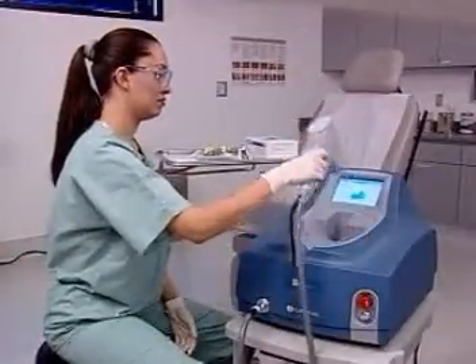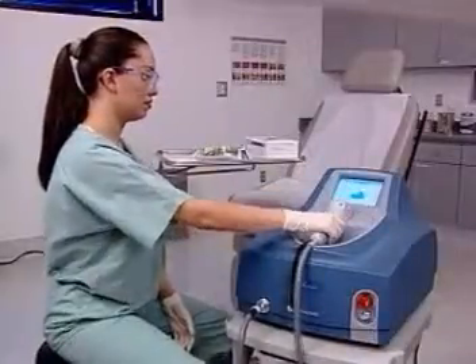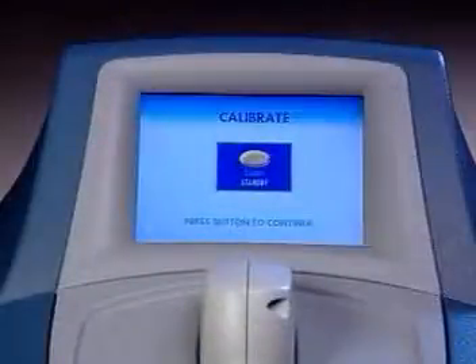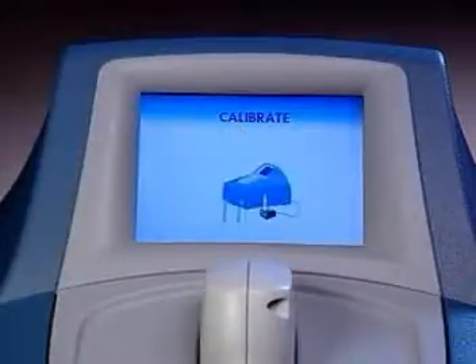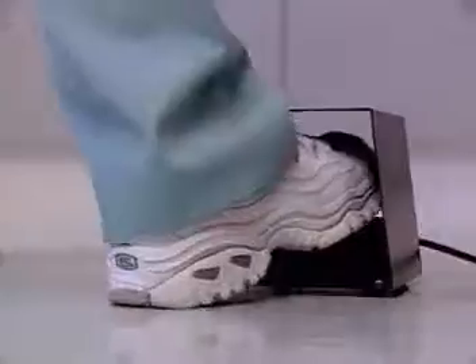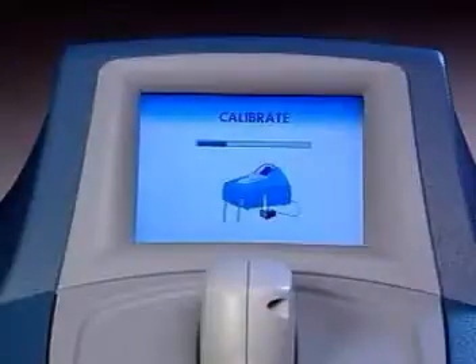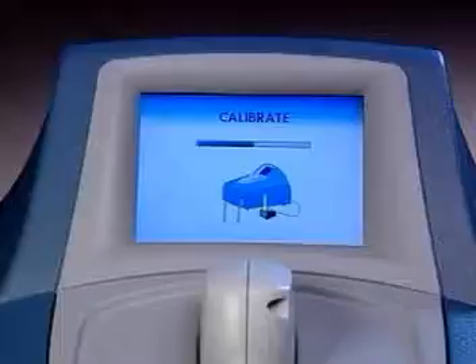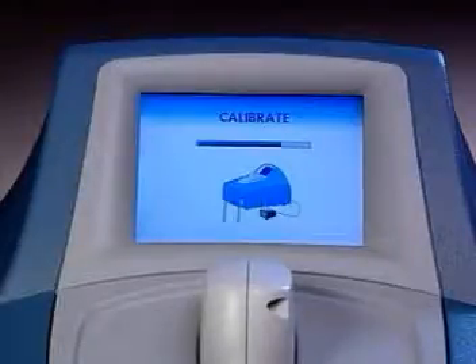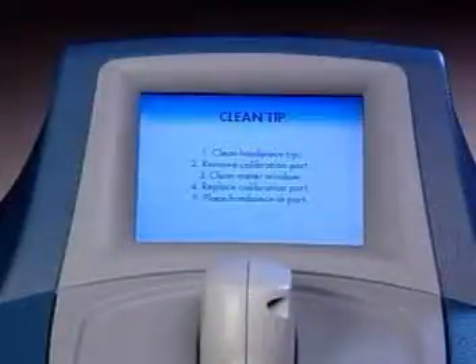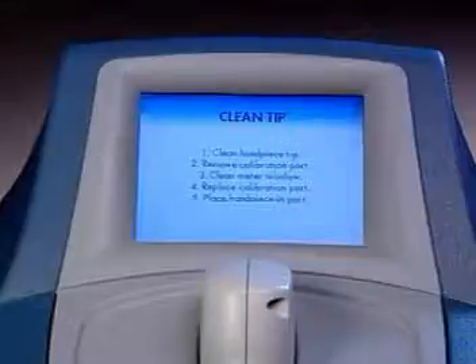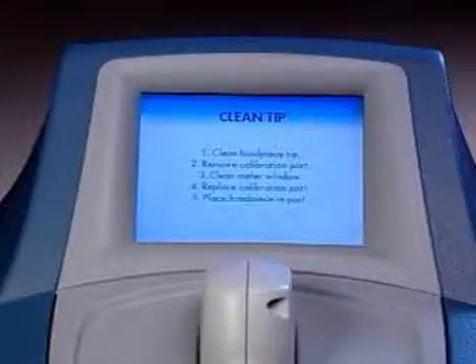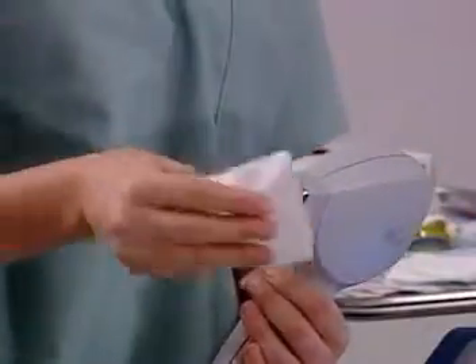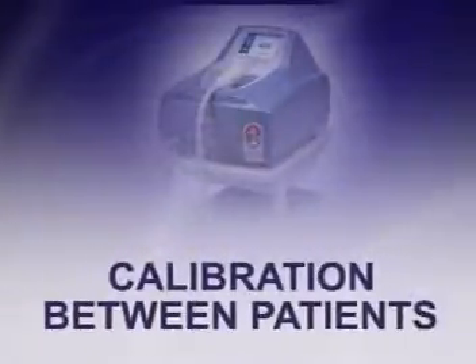Lift the handpiece from the calibration storage port. Reinsert the handpiece. Switch the system to Ready mode. When the foot switch icon appears on your touchscreen, step on the foot switch and keep it pressed during calibration. Calibration progress is displayed on the touchscreen. Release the foot switch when calibration is complete. If your system measures an abnormal reading, recommendations will be given as to possible fixes on the touchscreen display. Often the problem is caused by dirt or moisture on the tip of the handpiece or calibration window.